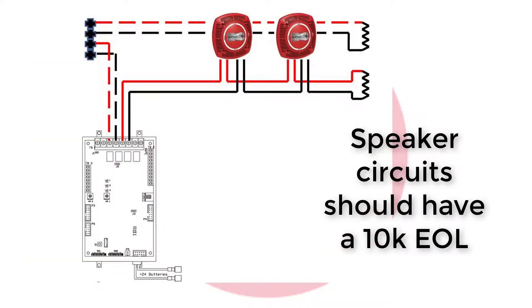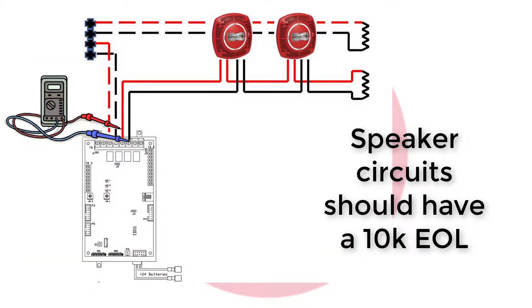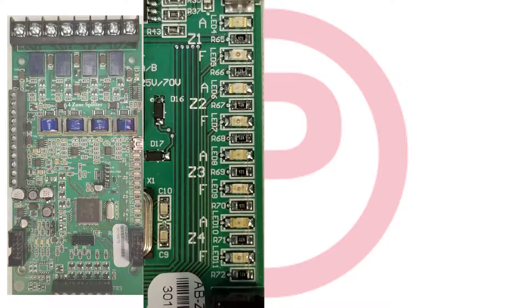If no zone splitter is installed, you will need to use your own meter to read for a 10K end of line resistor on the speaker circuit wiring on terminal block 1, terminals 5 and 6. If a zone module is present, then you will need to refer to the LEDs on the zone module to determine which speaker circuit is open.